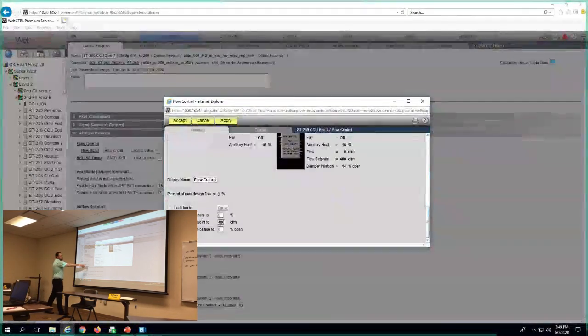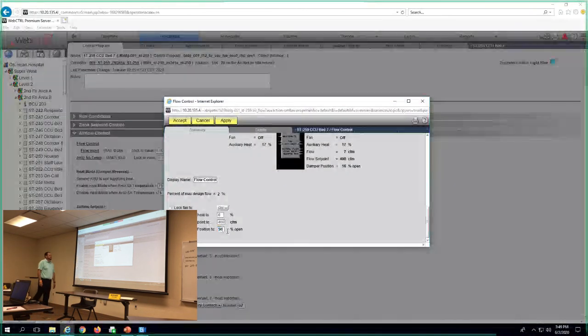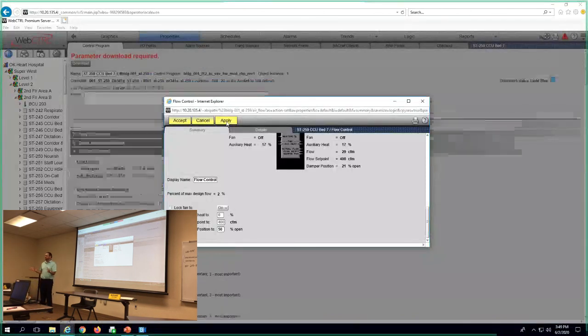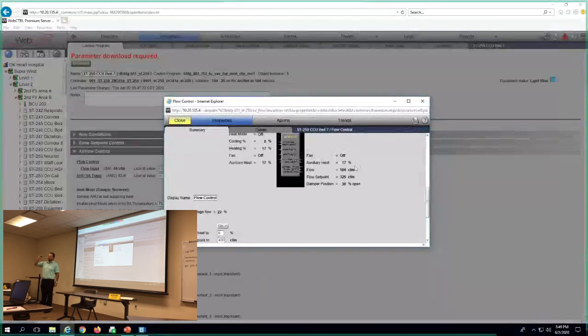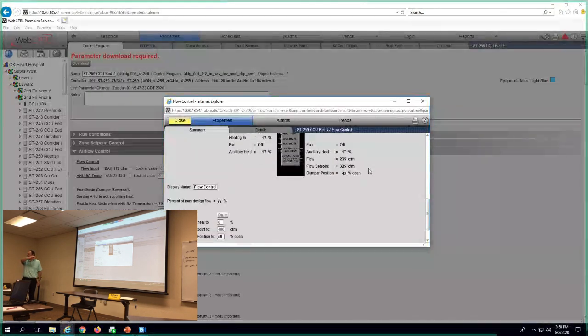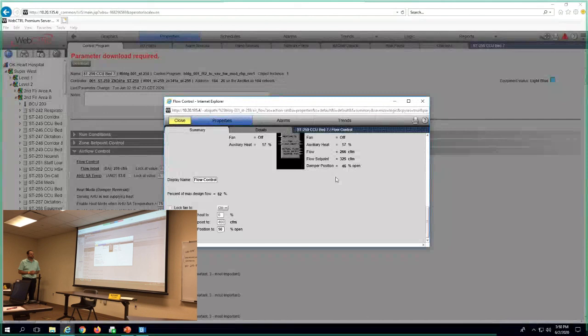You can also override it to a particular position. So there, you can clear that. If you're troubleshooting something, trying to figure out whether we have an airflow problem or whether the damper is the issue, there are a ton of fire smoke dampers in this building. If you look at the VAV and you've got zero airflow on it, I would be willing to bet it's a fire smoke damper, something like that, that's tripped. But there are some tools behind the scenes here that you can use to override things. Open, close, watch the airflow increase, decrease, to verify that the damper is operating properly.